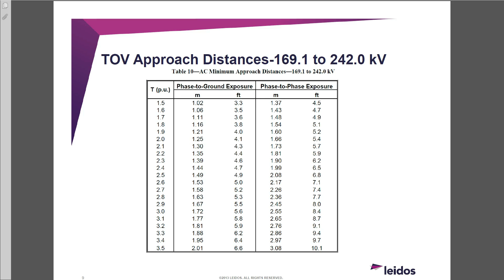These numbers, this is from 121 to 145 -- I apologize, this should look a lot more clear on my laptop. It's really not that bad, even when you get to 242 you're still at 6 feet, but as you rise in voltage, you're now at 16 feet between 420 and 550, and if you're so lucky to have a 745 kV line in your system, you're at 22 feet that you can't get near your energized equipment.